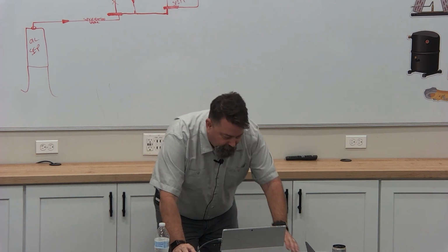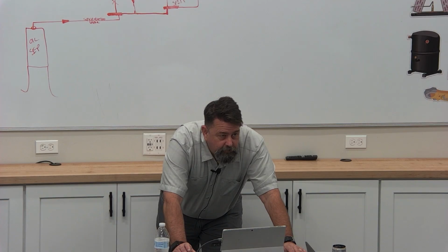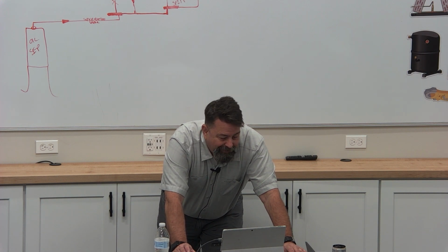So the other bit I want to discuss here is I've got a plenum coil set up here, all right? We're going to talk about the plenum and the coil in a minute, but just notice where that is. In order for this to work, my fan is sucking this air through this plenum and through my coil. That's my airflow. So if anything goes wrong with this deck pan situation, I'm not pulling through here anymore. I'm pulling through here. Okay? So my deck pans are critical. All right? If I take my deck pan up, my air curtain is definitely going to be disturbed.